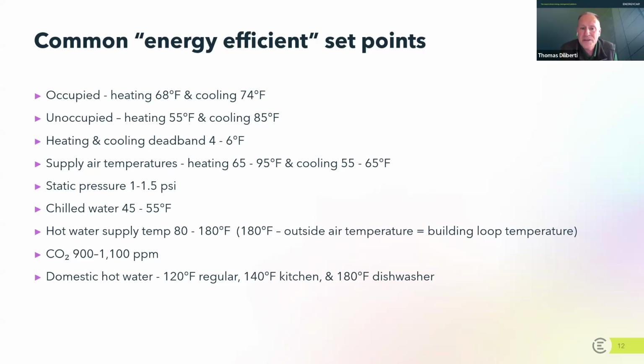And you might be seeing those numbers and going, wow, those numbers are much broader than what I would expect. And what I would say with a word of caution is that your unoccupied set points need to reflect how your organization functions and also how your systems perform. What I mean by that is I would not recommend low unoccupied set points for heating and cooling if your systems are, say, 40 years old and they're limping along and near the end of their life cycle. But if you have more robust systems that are able to recover and drive temperature change, then the way you're going to save a lot of energy is by having more aggressive setbacks. So I offer these as two numbers to consider, but you have to go back to your organization and your buildings. And even within your organization, you might find some buildings behave very well and perform very nicely with aggressive heating setbacks of 55.